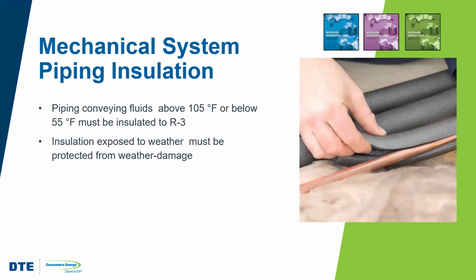Right. So on the mechanical side, we want to have some insulation around that piping, right? This is going to help to maintain water temperature and reduce heat losses, which could have a negative impact on the energy efficiency of the system, right? So if we've got fluid that's being transported and it's above 105 degrees, which it would be for a heating system, right, it's going to be insulated to R3, right?